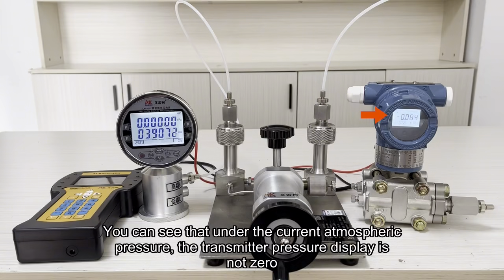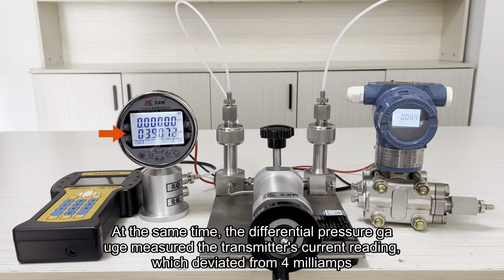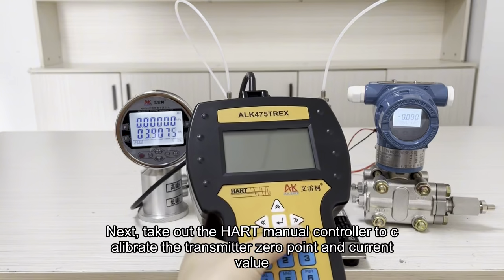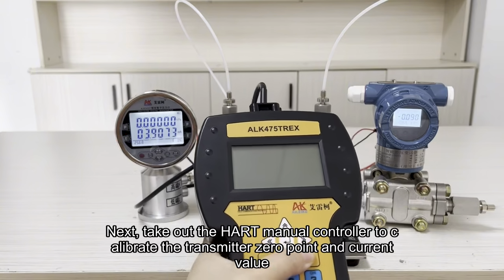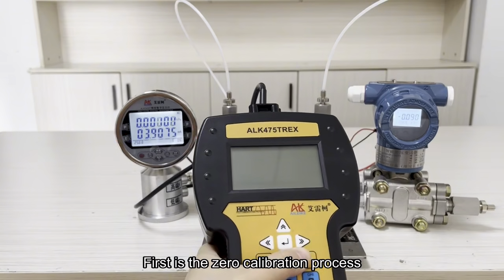You can see that under the current atmospheric pressure, the transmitter pressure display is not zero. At the same time, the differential pressure gauge measured the transmitter's current reading, which deviated from 4 mA. Next, take out the HART handheld controller to calibrate the transmitter's zero point and current value. First is the zero calibration process.